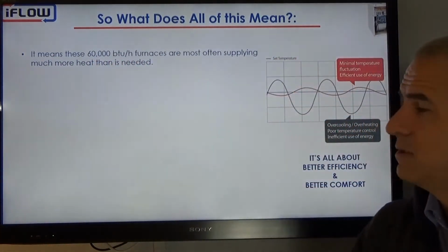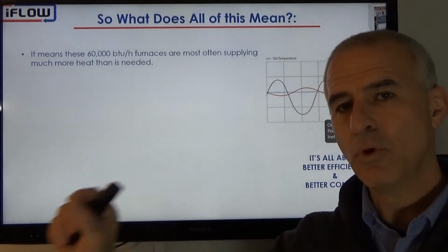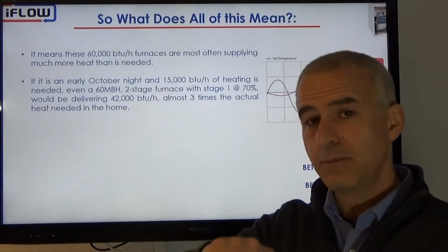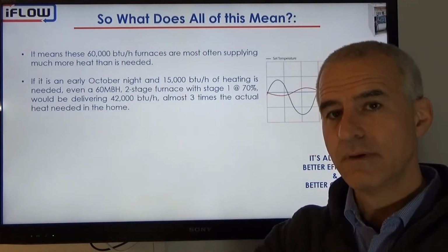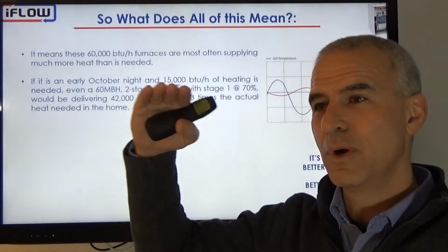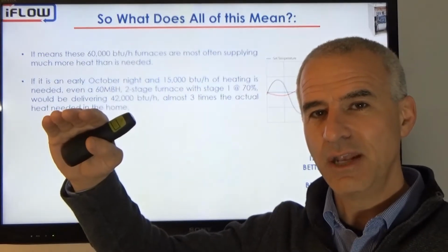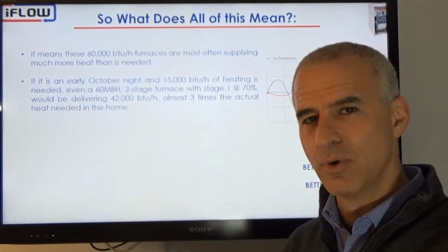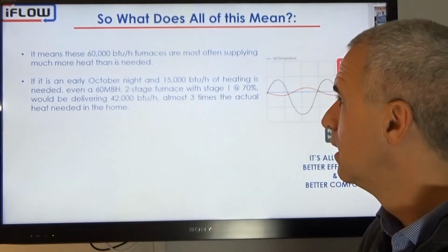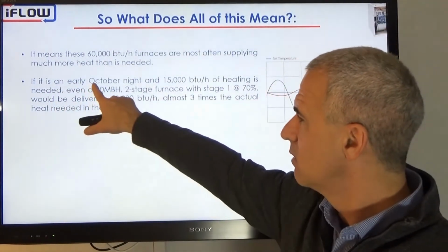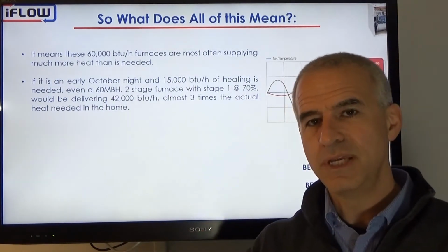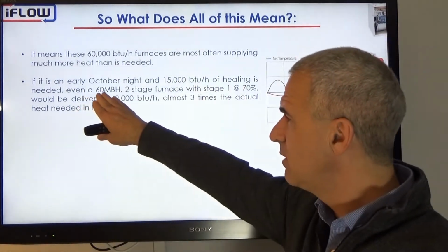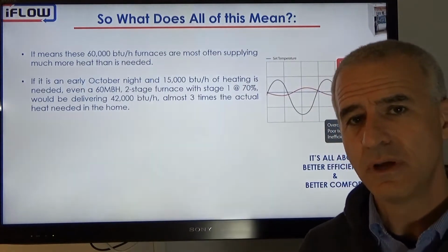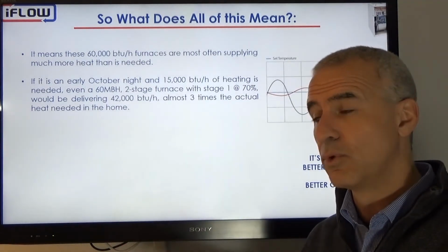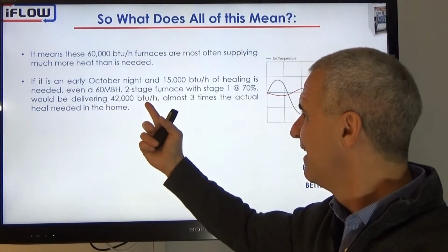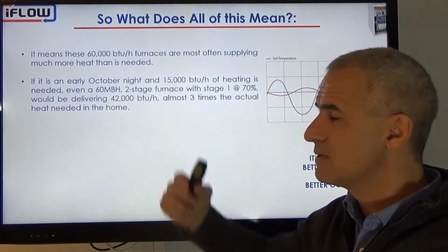The 60,000 BTU furnaces are most often supplying more BTUs than are actually needed, especially when we think of the seasonal curve, right? Those 60,000 BTUs are what we would need in a house in the middle of January. But what about September, October, November, March, April? So let's assume it's an early October night and we need about 15,000 BTUs in the home. So even with our 60,000 BTU 2-stage furnace, which we saw the minimum input was 42,000 BTUs, that's almost 3 times the 15,000 BTUs that we need.